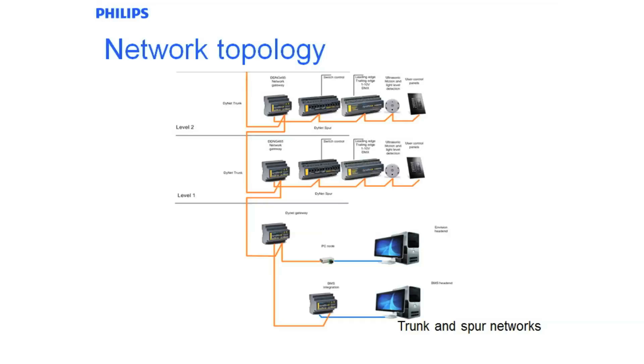These devices, as well as giving message translation between DyNet 1 and DyNet 2, also give us optical isolation. So if we have a major catastrophic fault on one spur on a particular level, it is not going to take out the entire building. It will only take out the network on that one segment.